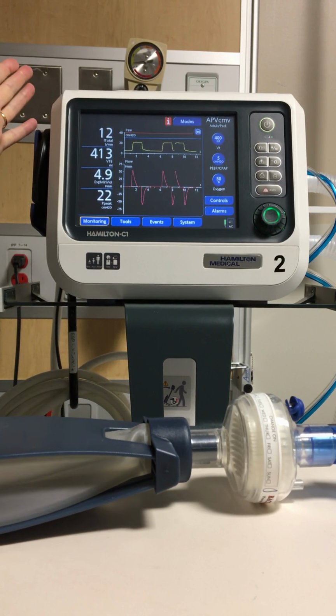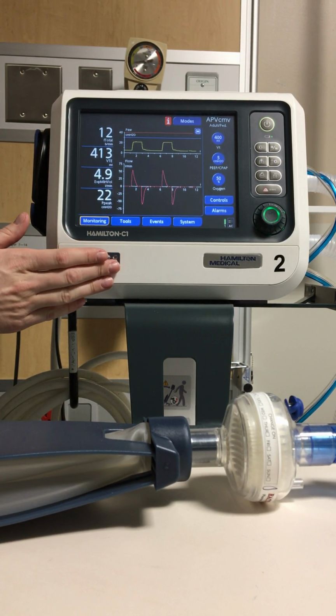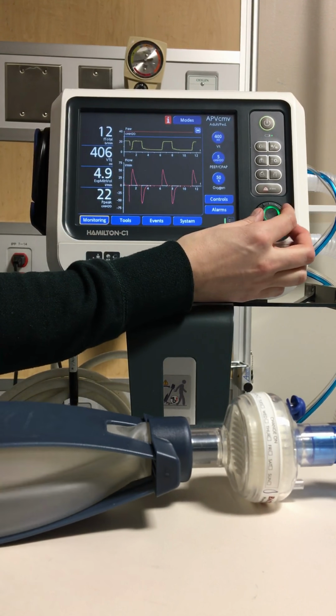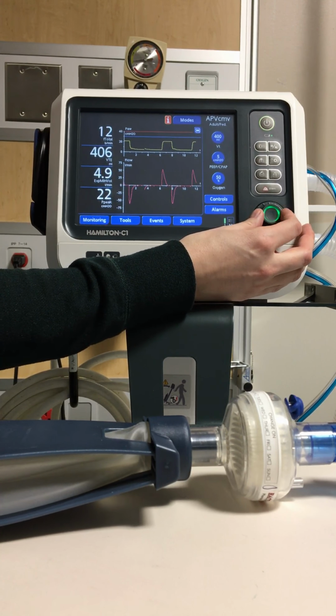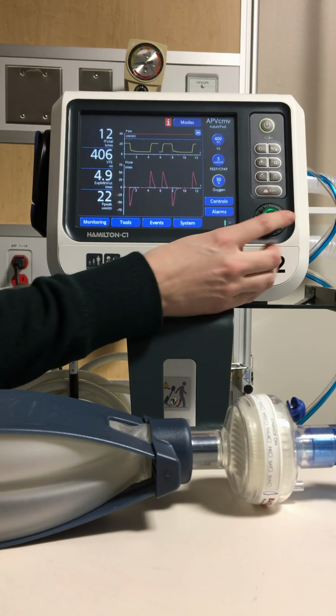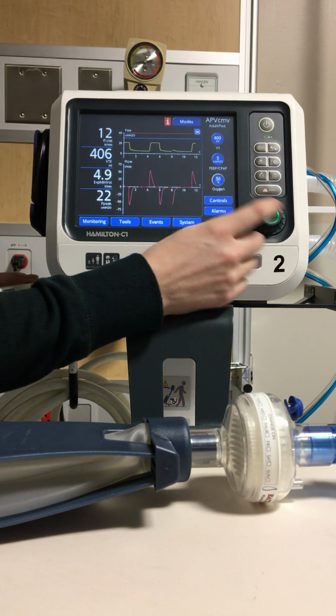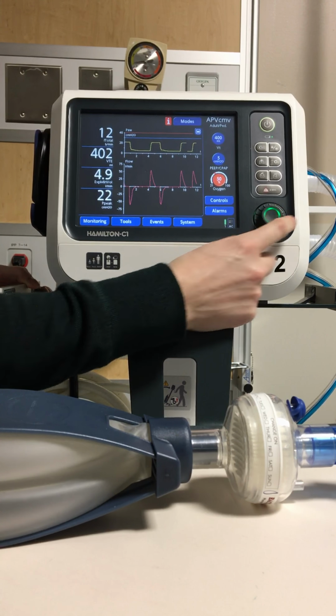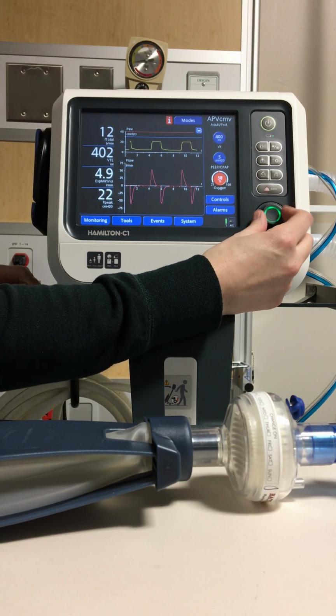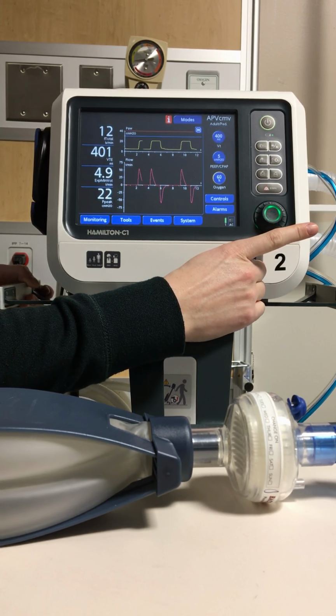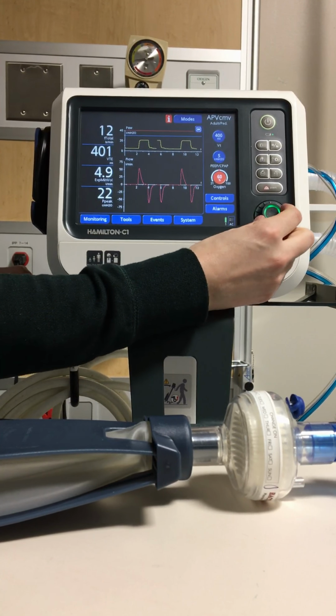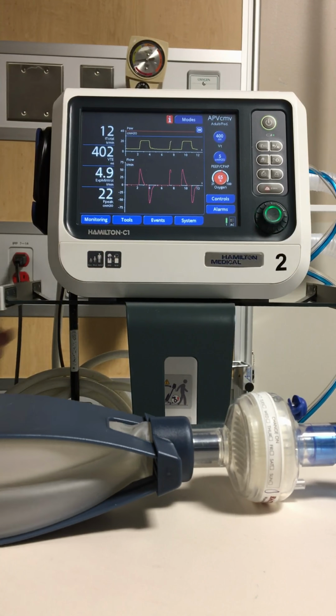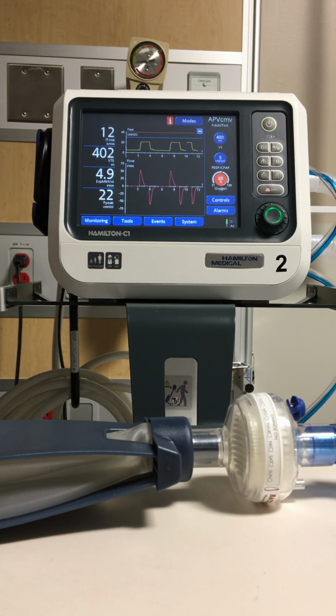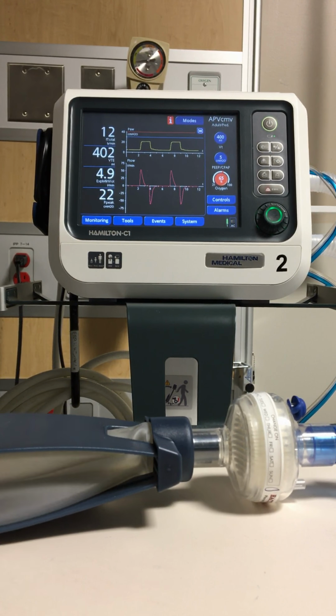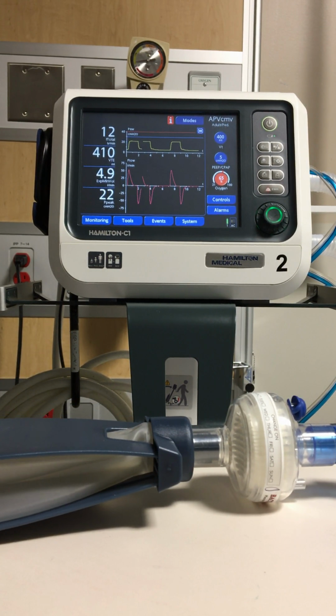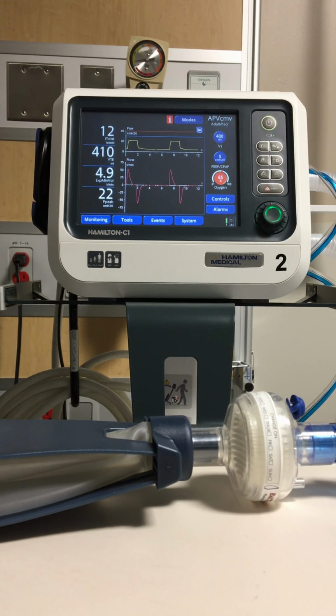I should say it is a touch screen, but sometimes the touch screen isn't as sensitive depending on if your fingers are cold, so if you needed to, you can always rotate through with the knob. Once it's yellow around the item that you would like, press, turn, and confirm. If you were to press and turn and not confirm, the value after a few seconds will default back to its original value. So this is the Hamilton C1 ventilator.